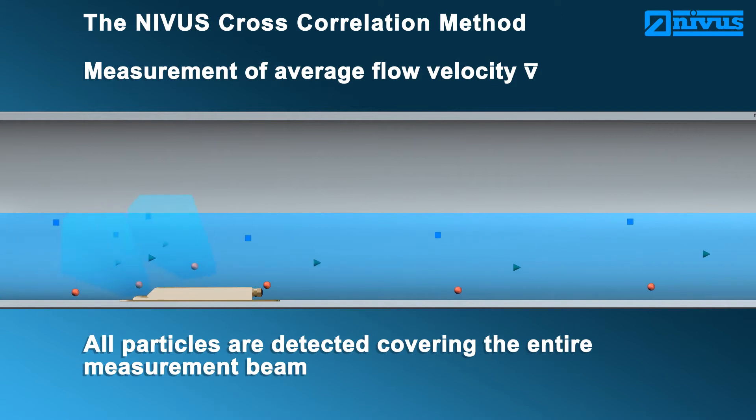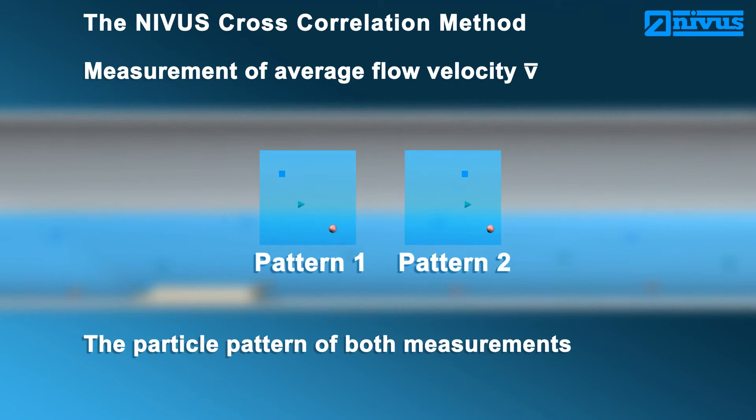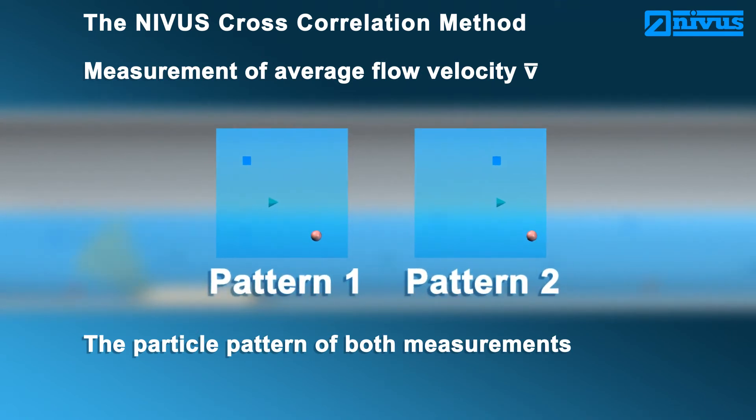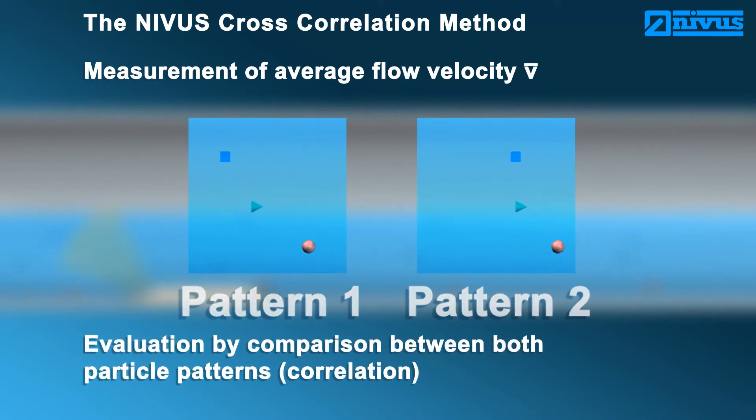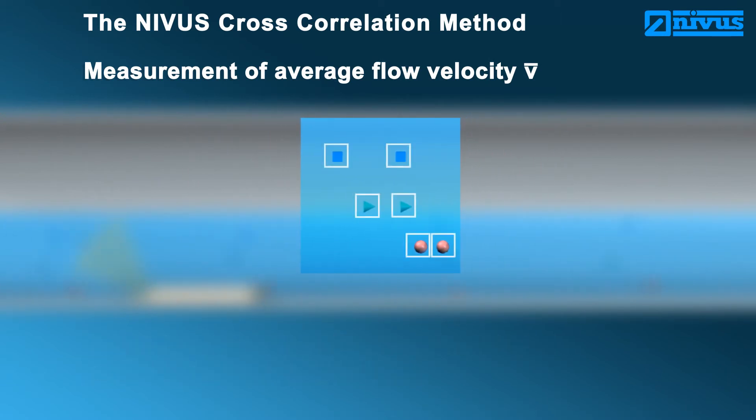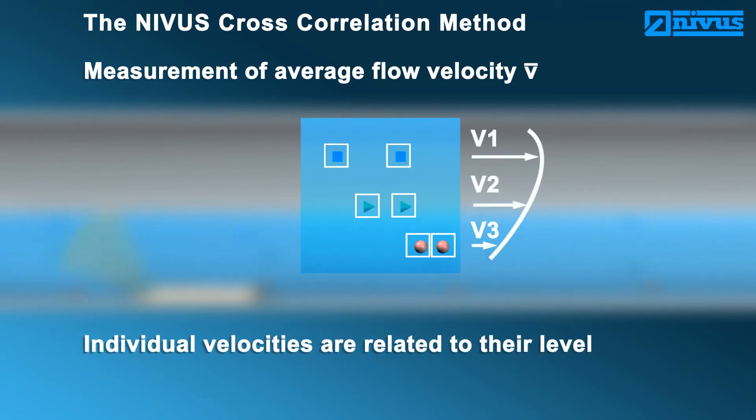The particle images are evaluated by comparing correlation to each other. This comparison repeats within a few milliseconds. In addition to the individual particle velocities, the relation to the flow level is available. Due to this, it is possible to represent the flow profile directly.